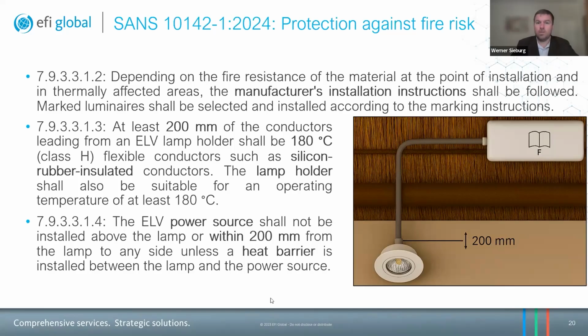Then the extra low voltage power source cannot be installed above the lamp or within 200 millimeters from the lamp to any side, unless a heat barrier is installed between the lamp and the power source. And the main reason for that is because the power source, very often being a switch mode power supply, also has a certain heating characteristic, gets hot, and if you then have two heating sources in close proximity to each other, they'll basically affect each other and cause further heating, and then also hazardous heating.